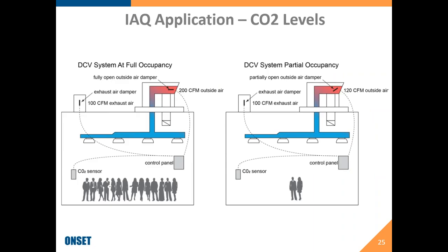So this specific diagram shows the result of using CO2 data loggers for a study of a commercial office building's parking garage. Following installation of these CO2 monitors, the individuals conducting this study were able to determine that there really was a heightened CO2 level at points in which people and cars were most active in that environment. They were able to do this by deploying the loggers in the area and then pulling a data set that looks similar to the following.